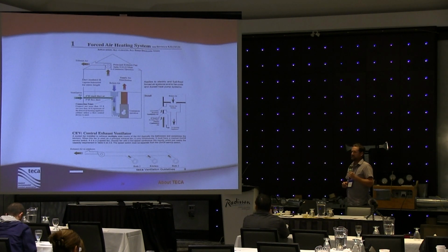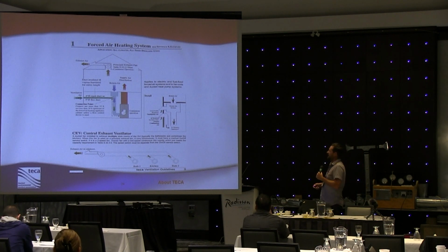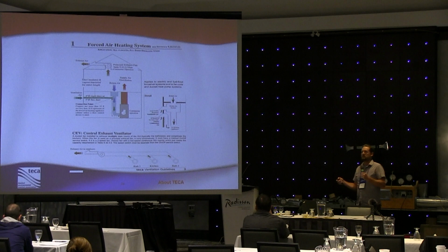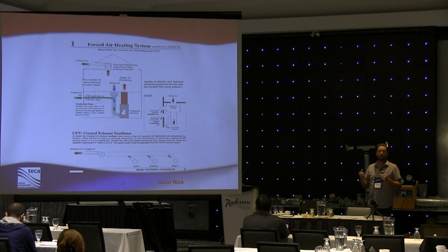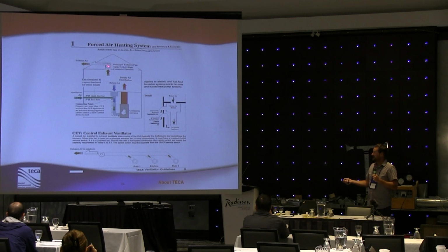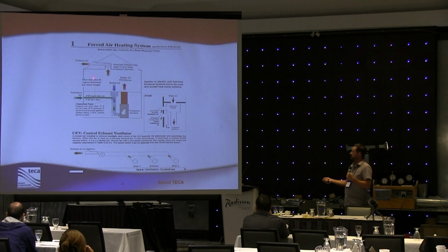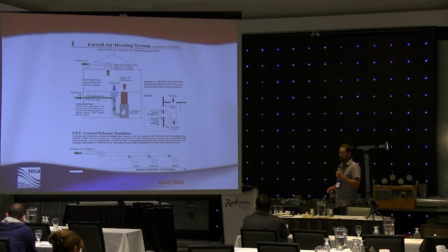We provide continuous ventilation because we found that, A, there's a need for it. We need to make sure that we're ventilating continually. And what we also did was we scaled back slightly on the ventilation rate so that we could allow for that fan to run 24 hours a day, 7 days a week. Like I said, typically this is a bathroom exhaust fan. This will be installed in a bathroom and it will run continuously.